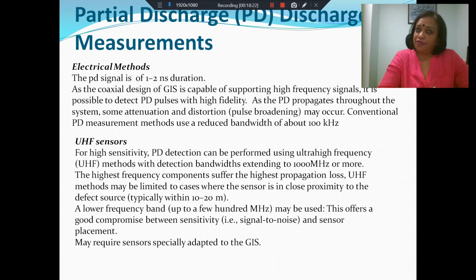detection. But then we also have the problem that the PD signal is an impact signal, so it has the entire frequency range, and we decide which range will give us a better signal to noise ratio with less noise, so we choose the ultra high frequency range. But even though there will be less contamination at high frequencies, the highest frequency components are also going to suffer the maximum propagation loss. So by the time it reaches the sensors, there might be considerable attenuation. UHF methods therefore may be limited to cases where the sensor is in close proximity to the defect source. Typically, if we expect the sensors to be within 10 to 20 meters of the source, we can expect the UHF method to work.